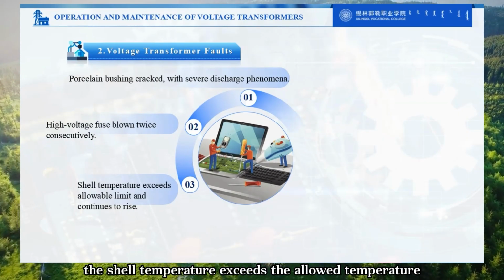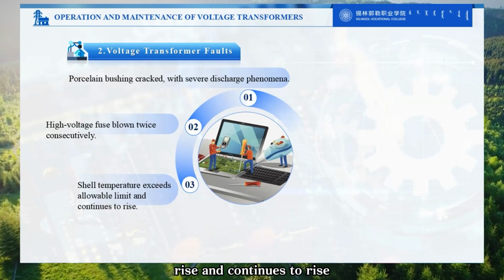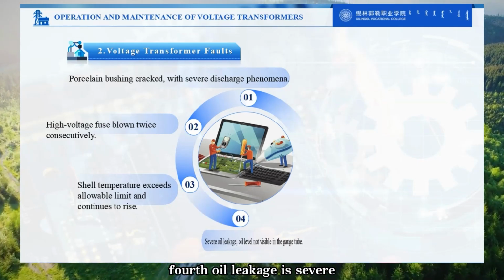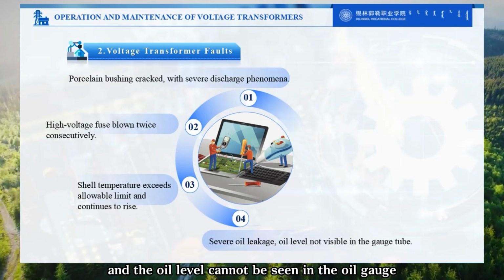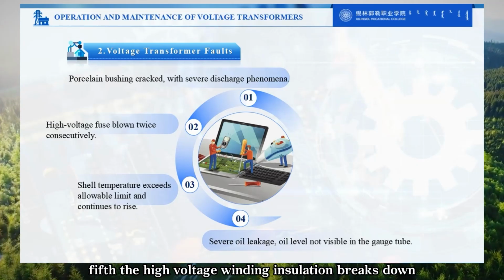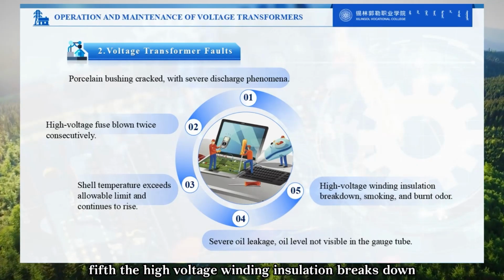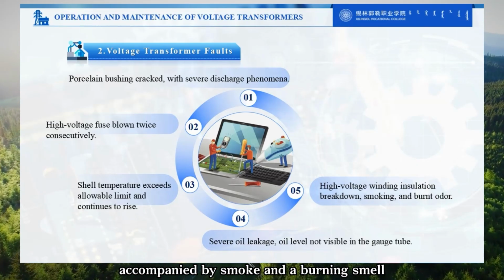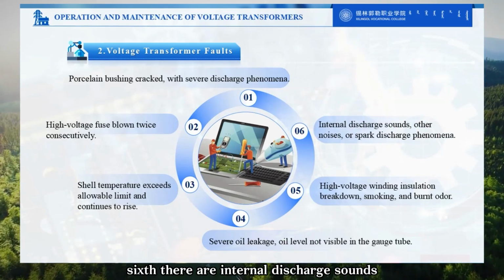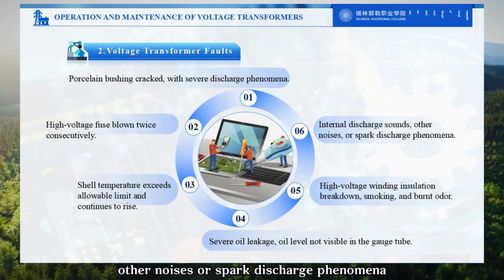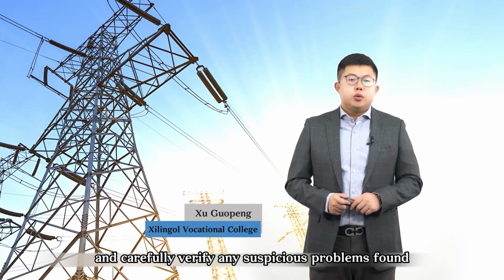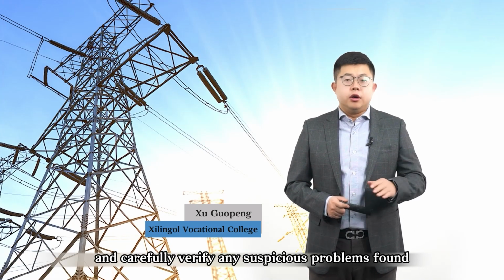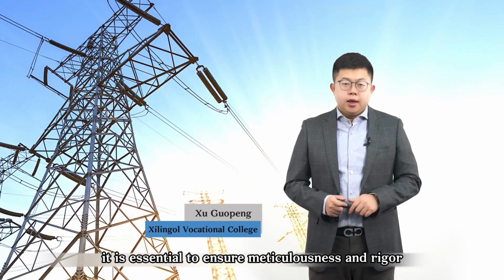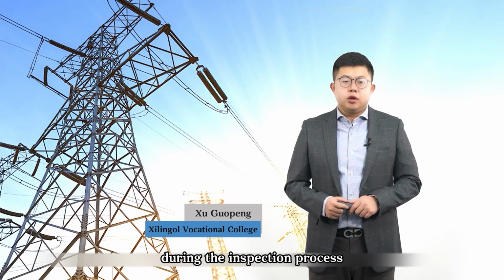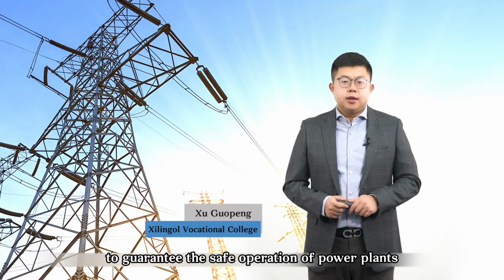Third, the shell temperature exceeds the allowed temperature rise and continues to rise. Fourth, oil leakage is severe, and the oil level cannot be seen in the oil gauge. Fifth, the high-voltage winding insulation breaks down, accompanied by smoke and a burning smell. Sixth, there are internal discharge sounds, other noises, or spark discharge phenomena. Everyone should combine the course content and carefully verify any suspicious problems found during work.